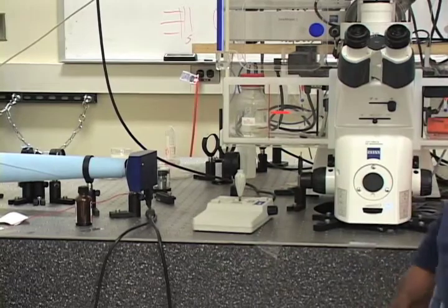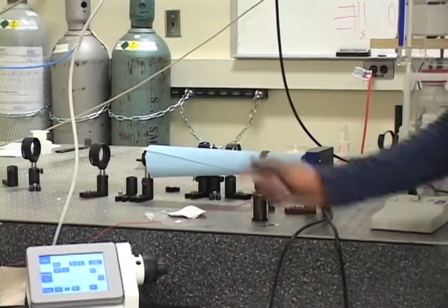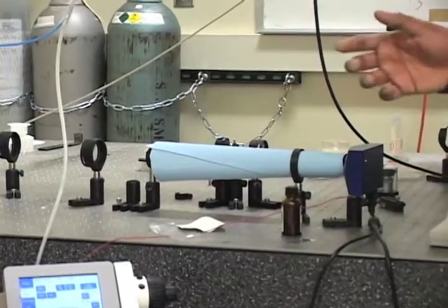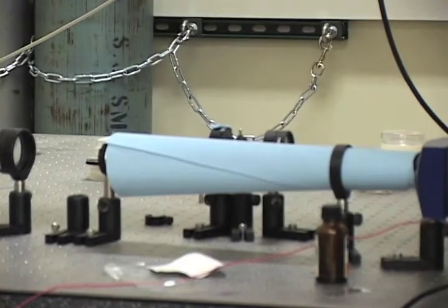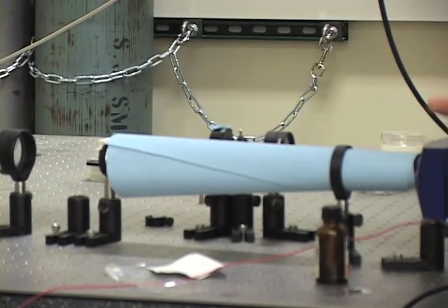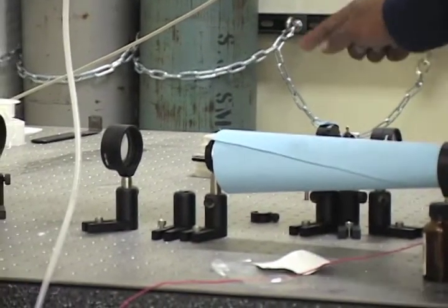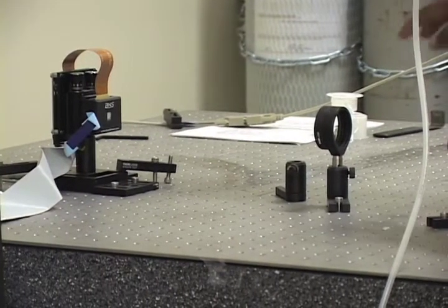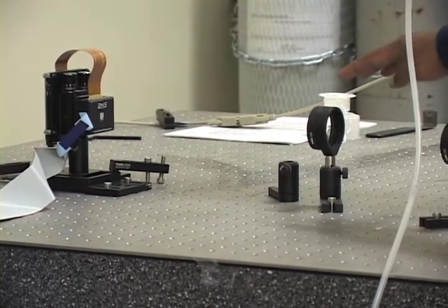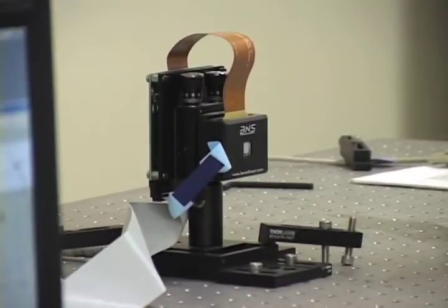so that we can properly fit it onto the aperture of our spatial light modulator. This component over here is a polarizer, and since we want to modulate only the phase of the field and not the amplitude, we have to polarize the light so that it's aligned with the fast axis of our liquid crystal modulator. After passing through this polarizer, this last lens over here is projecting the back focal plane of the objective onto that final component, which is the liquid crystal phase modulator.